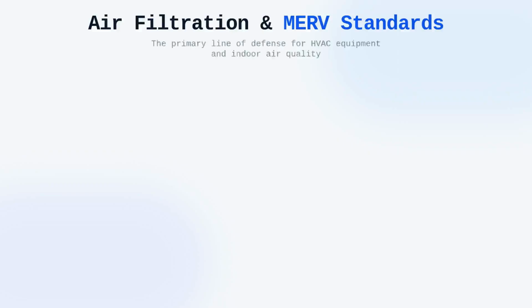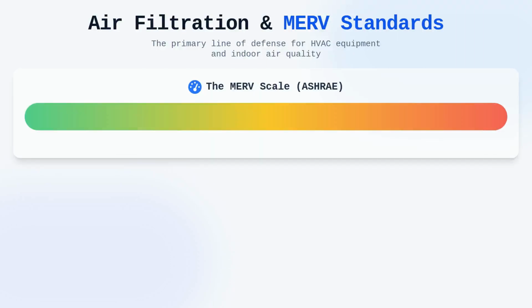Air filtration is the primary line of defense for both the HVAC equipment and the indoor environment, yet its complexity is often overlooked. At the heart of this discipline is the Minimum Efficiency Reporting Value, or MERV, a scale developed by ASHRAE that ranges from 1 to 16. This scale provides a standardized method to quantify a filter's ability to capture particles between 0.3 and 10 micrometers.